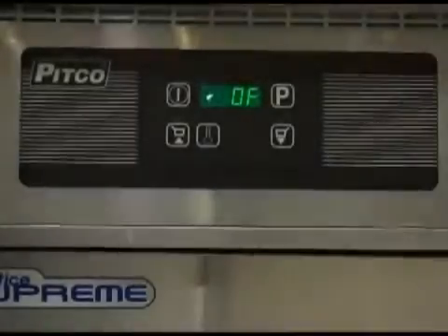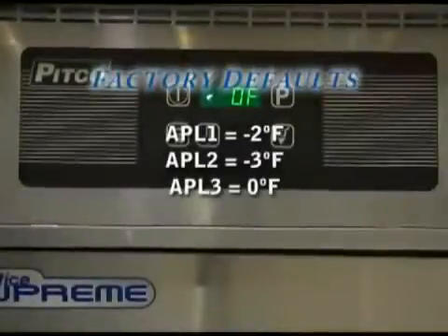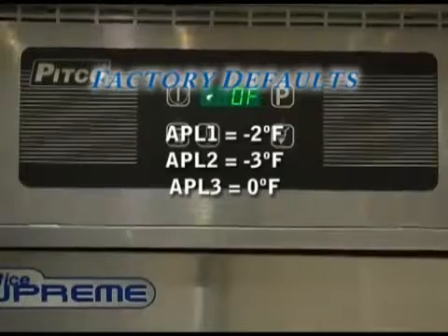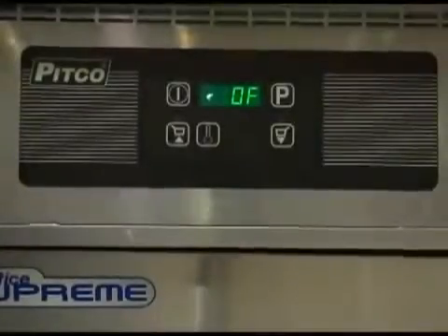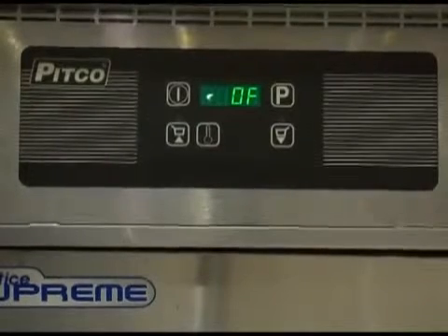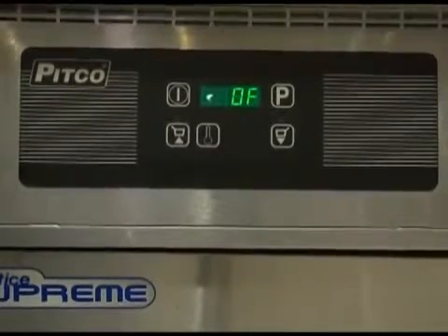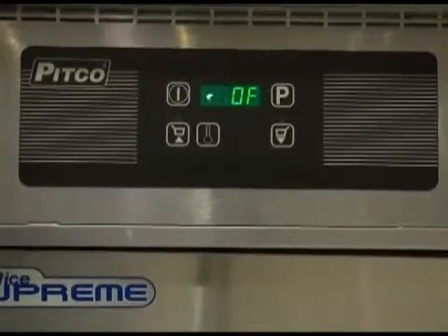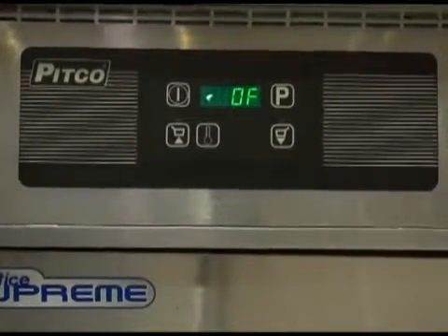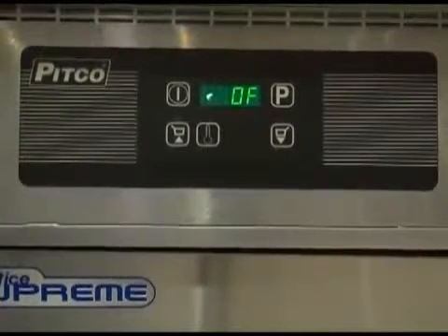The factory default values are as follows. APL1 equals negative 2 degrees Fahrenheit. APL2 equals negative 3 degrees Fahrenheit. And APL3 is 0 degrees Fahrenheit. Proper equipment and expertise is required to properly adjust this value. Keep in mind that even small changes may negatively affect cooking performance. Once set correctly, press the program key to save and continue to the next option.